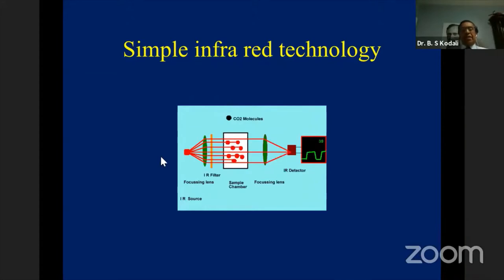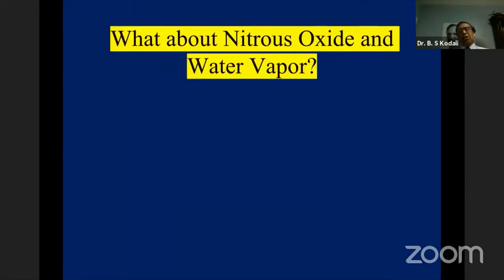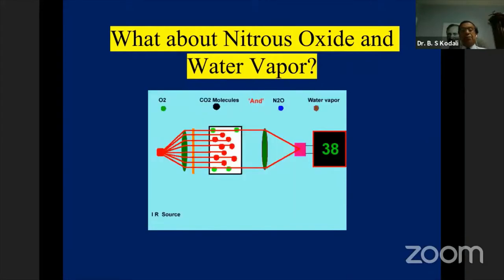CO2 is a polyatomic gas that absorbs infrared light at 4.3 microns — that is the wavelength where CO2 molecules absorb. Nitrous oxide and water vapor, also administered during anesthesia, are also polyatomic gases and absorb infrared light as well. Therefore, many monitors provide automatic corrections for the errors produced by nitrous oxide and water vapor.